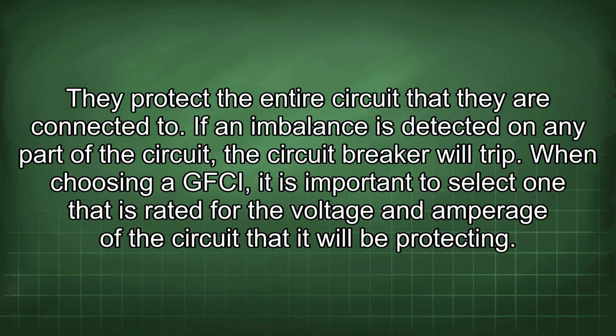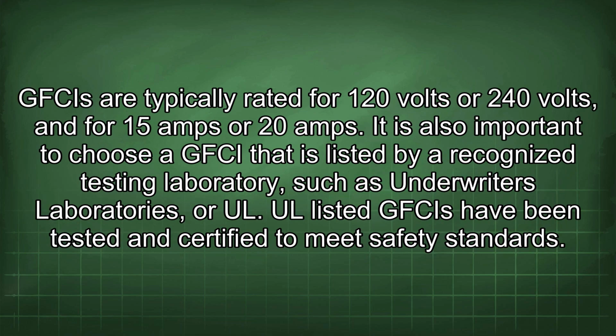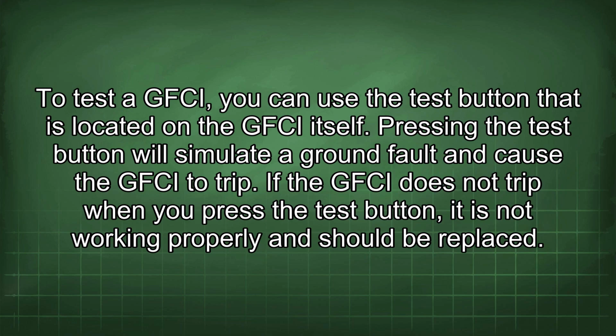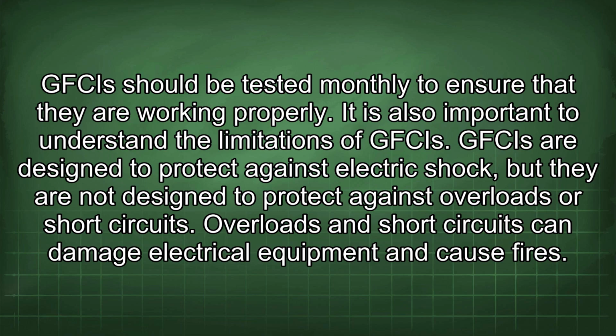When choosing a GFCI, it is important to select one that is rated for the voltage and amperage of the circuit that it will be protecting. GFCIs are typically rated for 120 volts or 240 volts, and for 15 amps or 20 amps. It is also important to choose a GFCI that is listed by a recognized testing laboratory, such as Underwriters Laboratories, or UL. UL-listed GFCIs have been tested and certified to meet safety standards. To test a GFCI, you can use the test button that is located on the GFCI itself. Pressing the test button will simulate a ground fault and cause the GFCI to trip. If the GFCI does not trip when you press the test button, it is not working properly and should be replaced. GFCIs should be tested monthly to ensure that they are working properly.